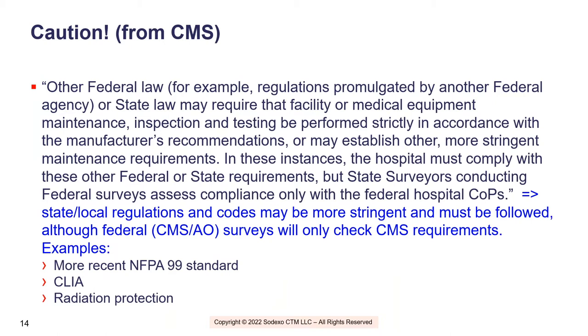This is just a word of caution. We're all from different states, and we all have different state or local guidelines to follow. Now, this is a point where the state does trump the federal. So if your state requires more stringent maintenance than AEM, there are certain states that require OEM required maintenance. I'm not going to call those states out, but you do have to follow those. Same thing with NFPA 99, CLIA, radiation protection. Florida, for instance, has adopted NFPA 99 2018, which is wonderful. Hopefully we can get the federal government to adopt those standards soon.